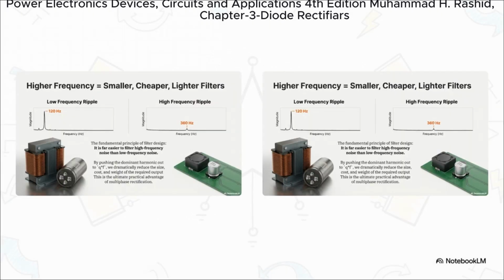And here's the payoff in the real world. Just look at the difference. To filter out low-frequency noise, like that 120 Hz ripple from a single-phase system, you need big, bulky, heavy, expensive components. But to filter out high-frequency noise, like the 360 Hz from our six-phase system, you can use components that are dramatically smaller, cheaper, and lighter. That is the ultimate practical advantage. It's a total game changer.